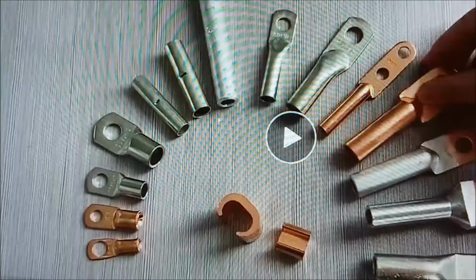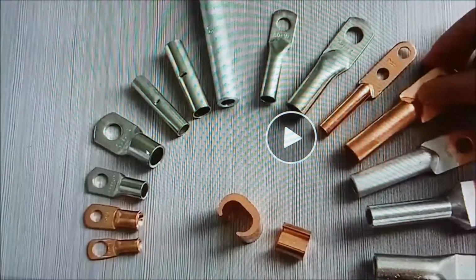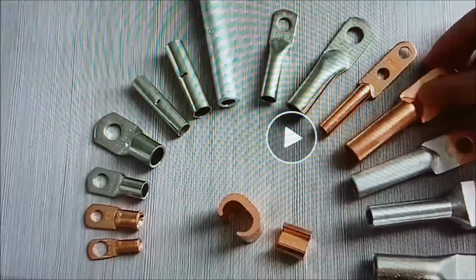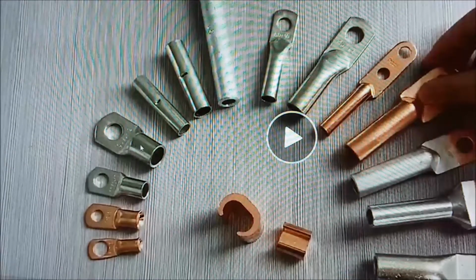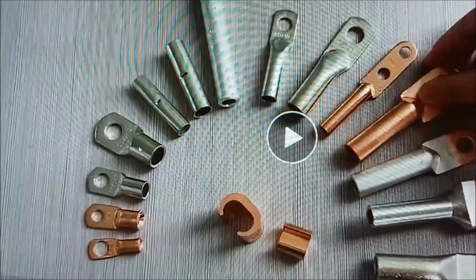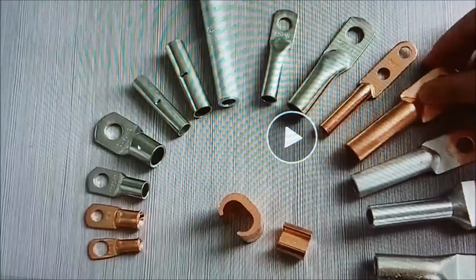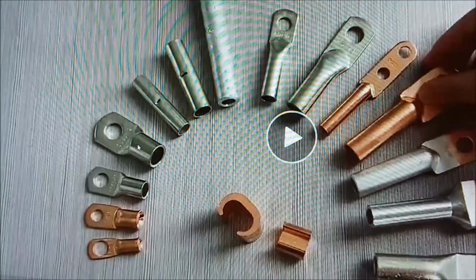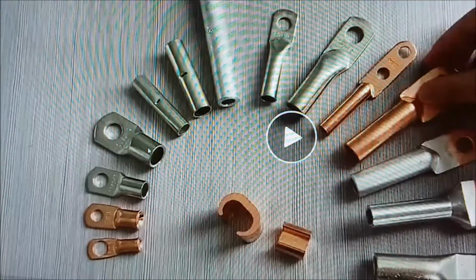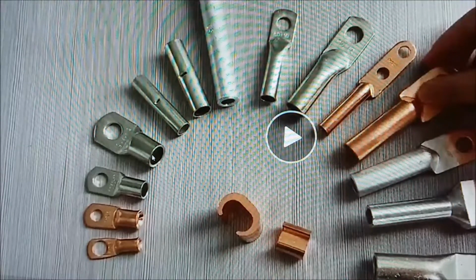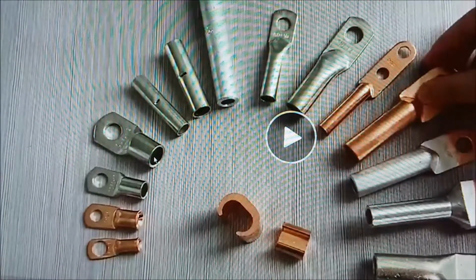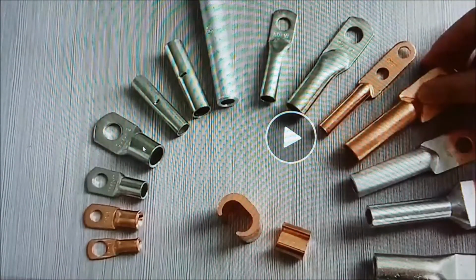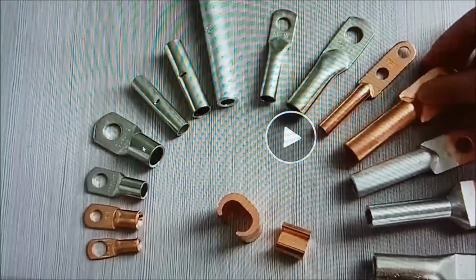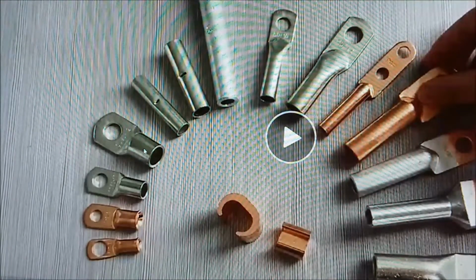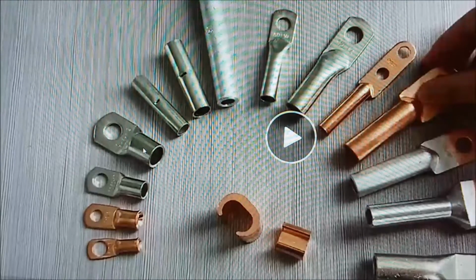Now, a standard terminal lug, you could find these in an auto parts store in the U.S. or an electrical supply house. They're made out of copper and then tin plated. The tin plate is for corrosion resistance. You get them to be a pretty tight fit on your wire, and then use a hydraulic crimper to smash them down. You can also solder them on. Being that they're tin, they take solder really well.